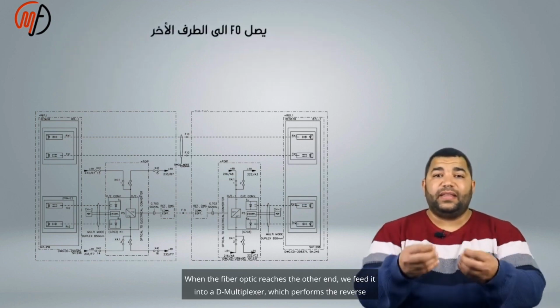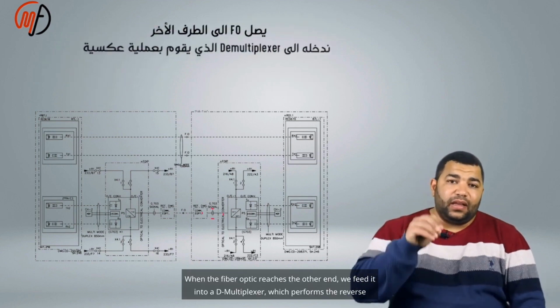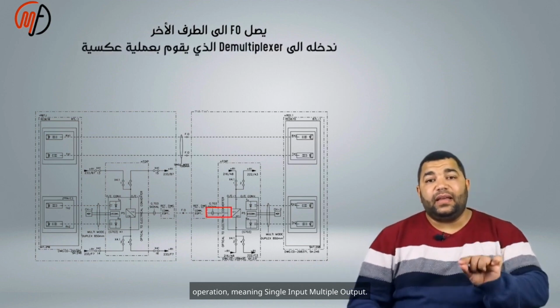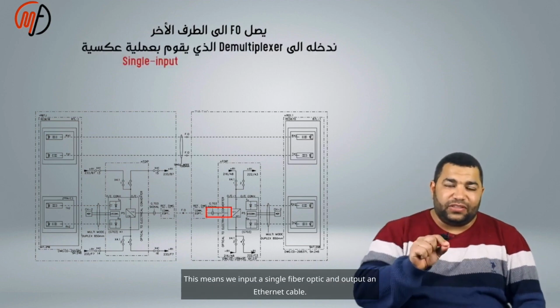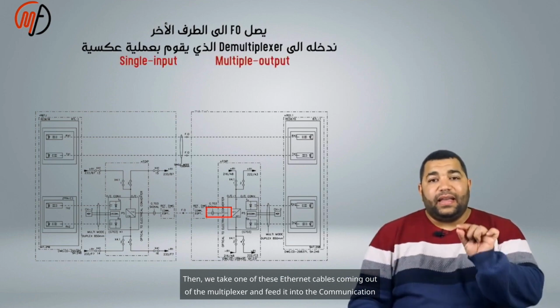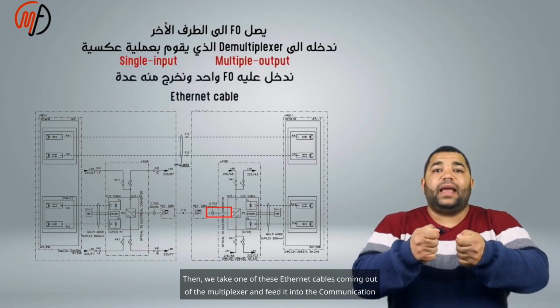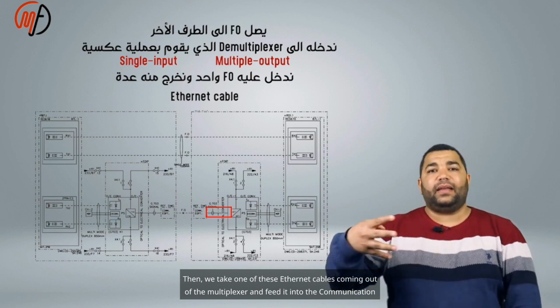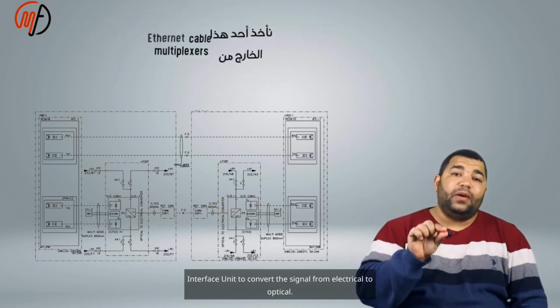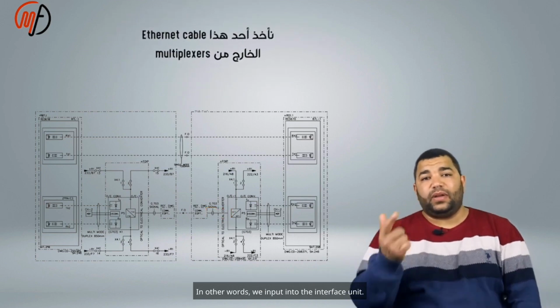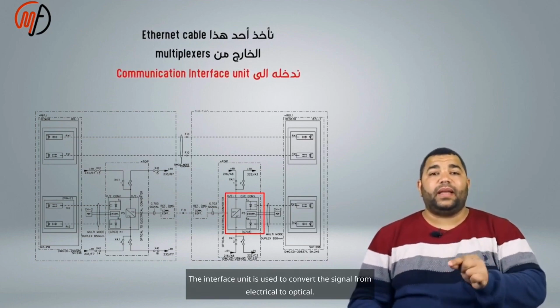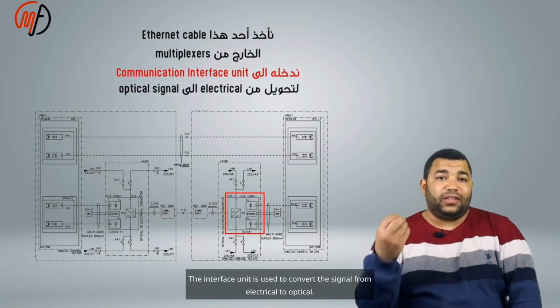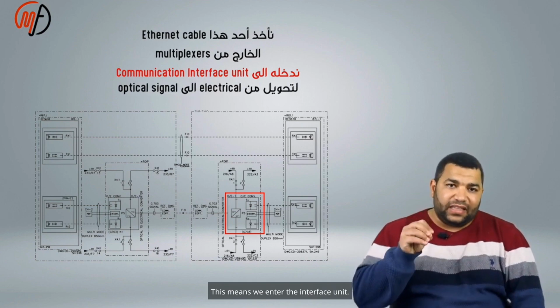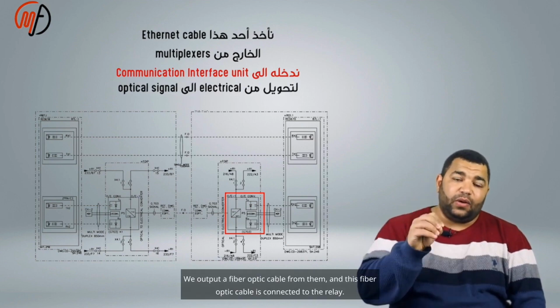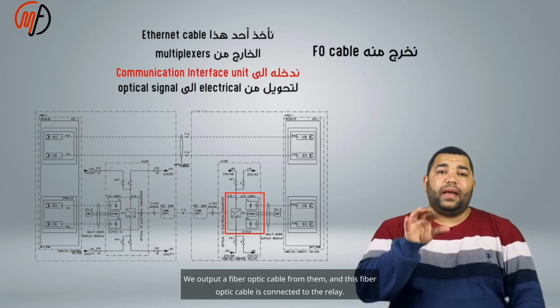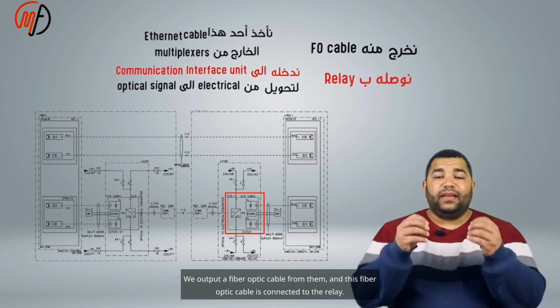When the fiber optic reaches the other end, we feed it into a demultiplexer, which performs the reverse operation, meaning single input, multiple output. This means we input a single fiber optic and output an Ethernet cable. Then we take one of these Ethernet cables coming out of the demultiplexer and feed it into the communication interface unit to convert the signal from electrical to optical. In other words, we input electrical into the interface unit, which is used to convert the signal from electrical to optical, and we output a fiber optic cable from it, and this fiber optic cable is connected to the relay.